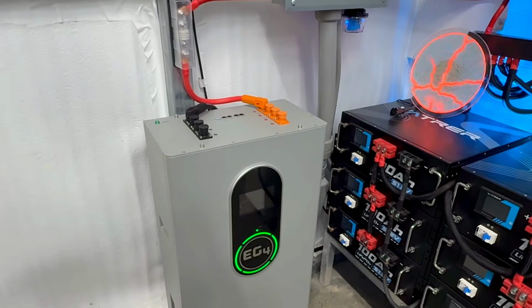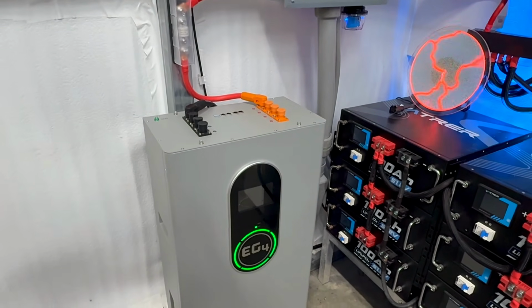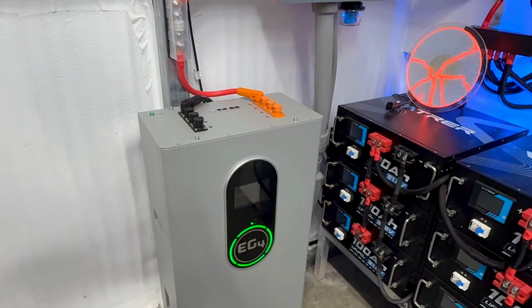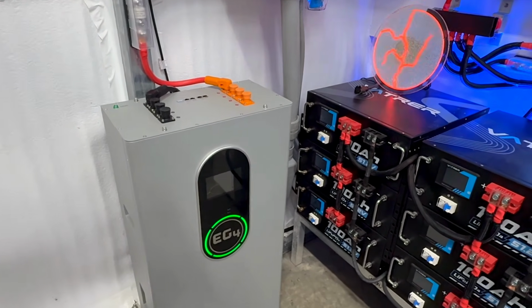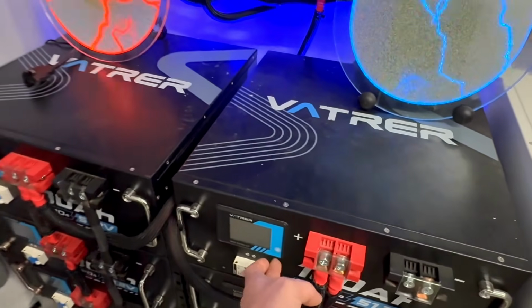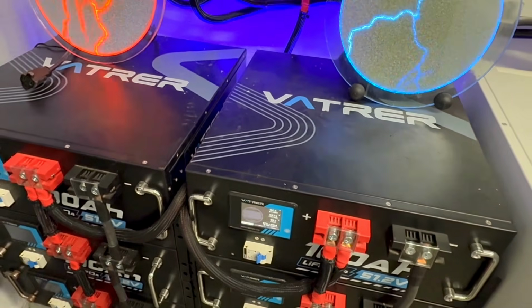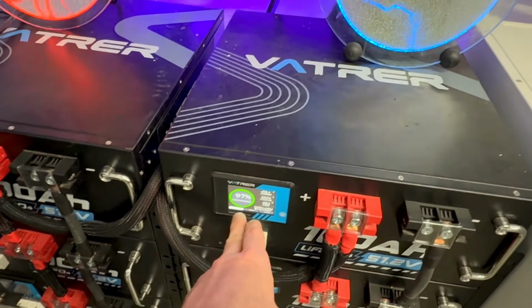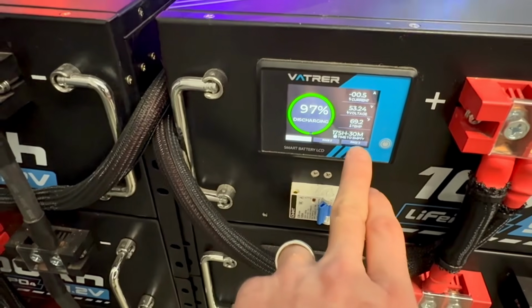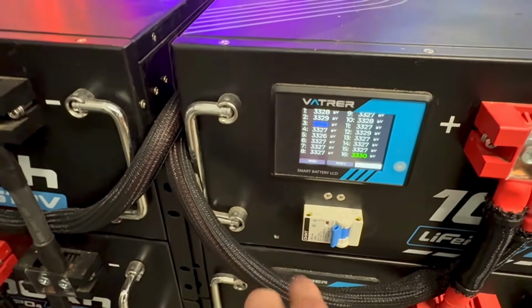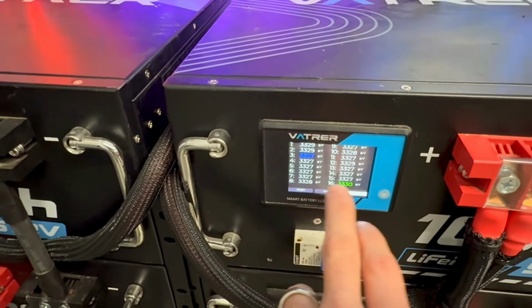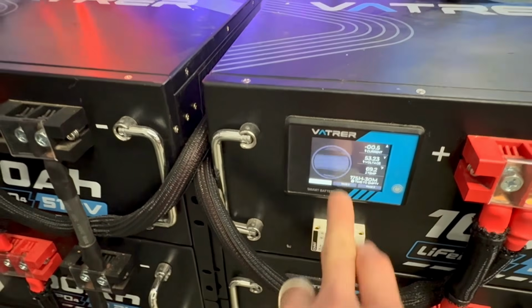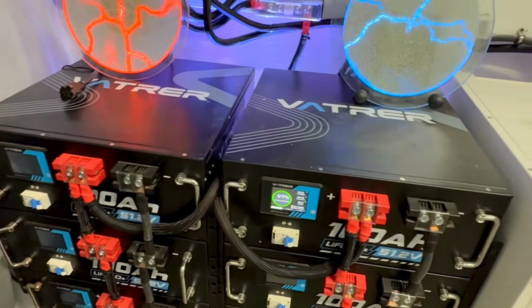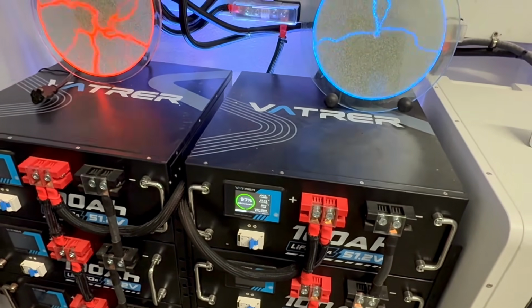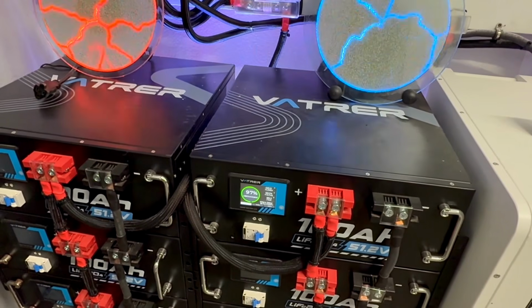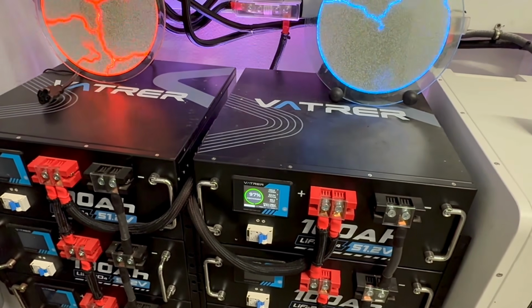You do not want to do that, because the discharge rate when you look at the voltage is very gradual, and you can have a very big difference in capacity between batteries while the voltage looks very similar. So don't necessarily go by voltage. You're going to want to fully charge the batteries up, and you can tell that because on each of the batteries, or at least the good ones, if the SOC says it's at, say, 100%, so these right here say 97.